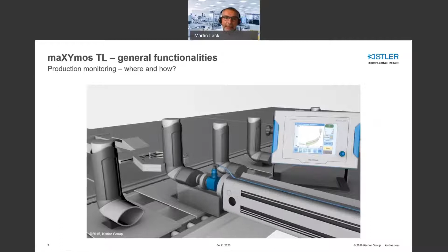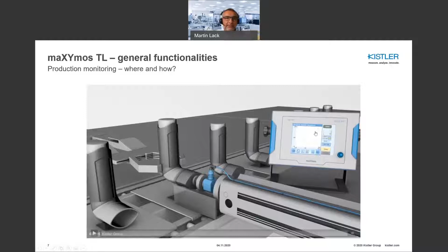Here you can see a connection at an inhaler. As the process runs, the force is measured, the displacement moves along with the cylinder, and in parallel with the fitting, you see the curve on the display passing through the evaluation objects—it's an okay fitting.